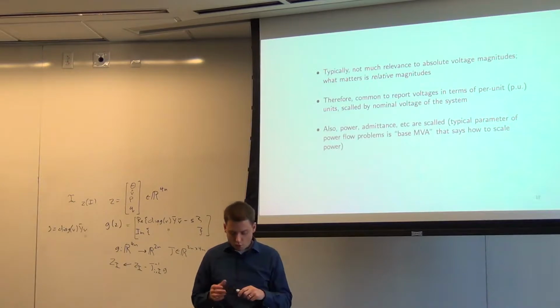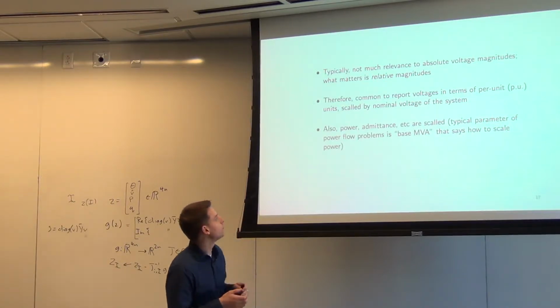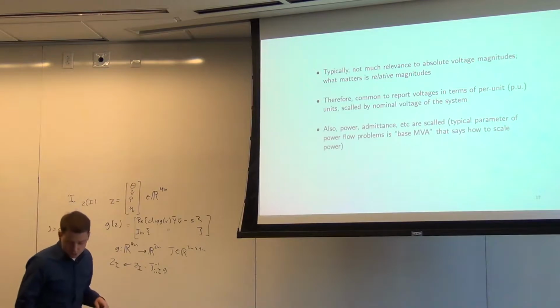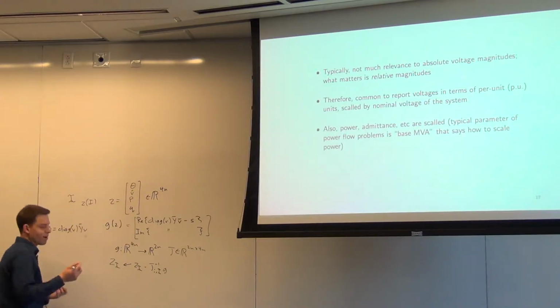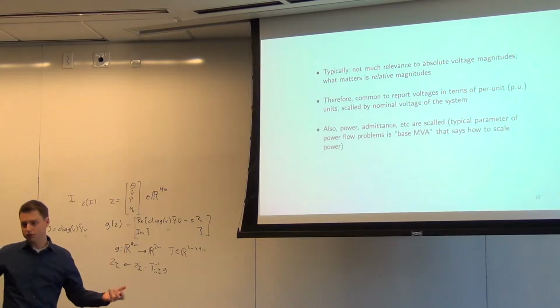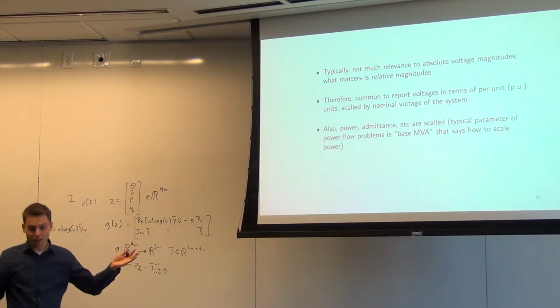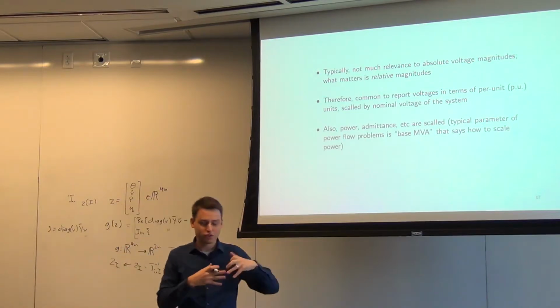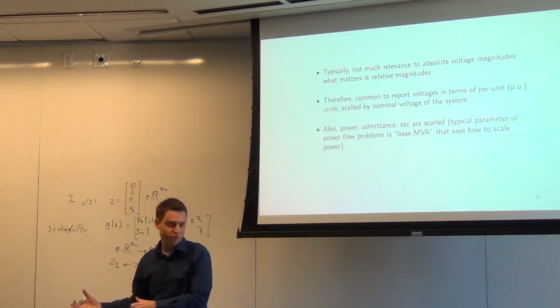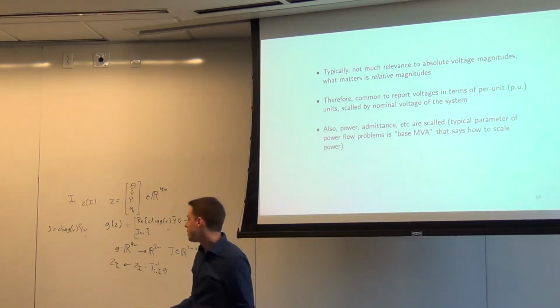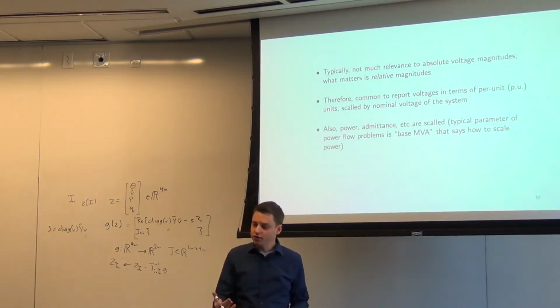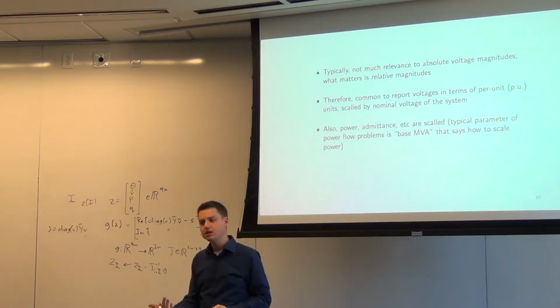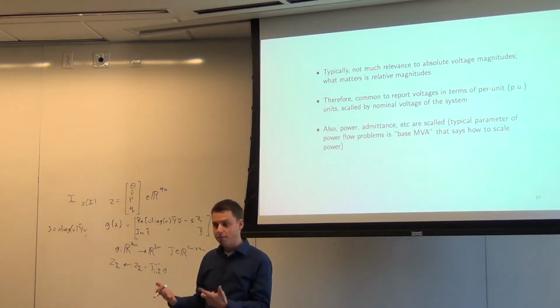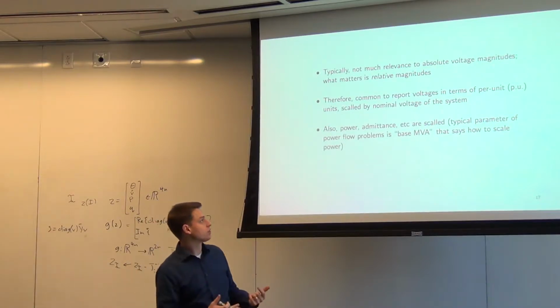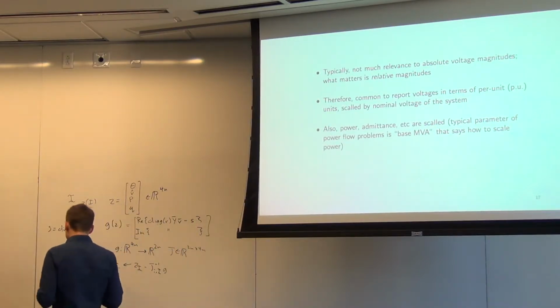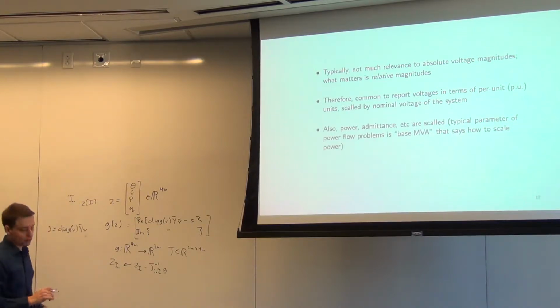First, when you see power flow, you'll often see something called PUs, so you'll see things reported. It's talking about voltage. Voltage should be in kilovolts or many different units, depending on the scale of things. It could be 100 kilovolts or 500 kilovolts, or if it's a smaller system, 10 kilovolts or something like that. Or for distribution, it can be even lower. But typically, the actual voltage and actual powers don't matter that much. What matters is the relative powers and relative voltages involved in the power flow solution. So what you'll often see is that voltages are scaled to what are called per unit quantities.